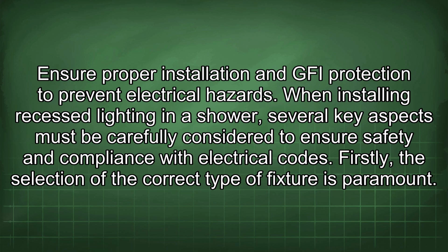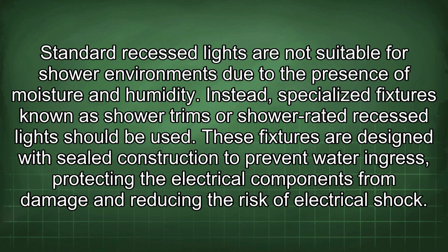When installing recessed lighting in a shower, several key aspects must be carefully considered to ensure safety and compliance with the electrical codes. Firstly, the selection of the correct type of fixture is paramount. Standard recessed lights are not suitable for shower environments due to the presence of moisture and humidity. Instead, specialized fixtures known as shower trims or shower-rated recessed lights should be used.